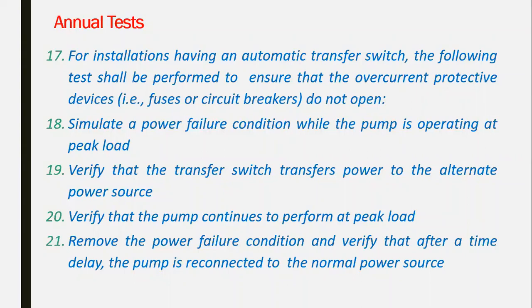After you remove the simulation and return the normal electrical supply to the system, the ATS will not immediately return to the normal supply. It will take a delay time. It depends on the size of the ATS and the rating. It takes something like 20 seconds, 50 seconds to transfer back from the generator to the normal supply. That's why there is a time delay before it connects back to the normal supply.